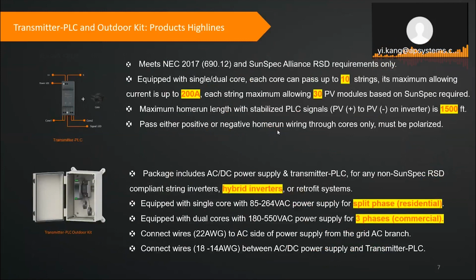The next is the transmitter. They call it transmitter dash PLC. This transmitter generates a PLC signal and follows the NEC standard and the SunSpec requirement. You see there are by default 2 cores. They have 2 channels in here, core 1 and core 2. But for most residential jobs, they do not need both cores installed for the transmitter, because most residential jobs will be less than 10 strings for sure. And each core, each CT they have here, can go up to 10 strings, even more.